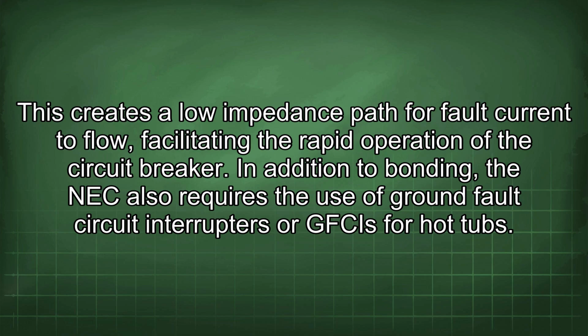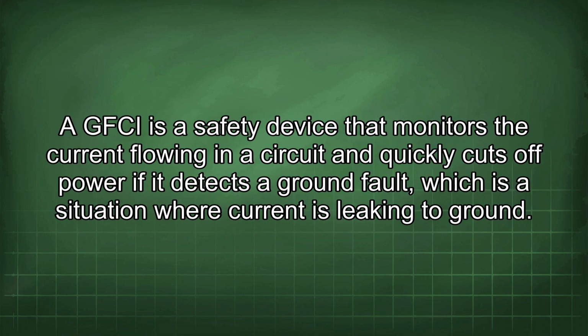This creates a low impedance path for fault current to flow, facilitating the rapid operation of the circuit breaker. In addition to bonding, the NEC also requires the use of ground fault circuit interrupters, or GFCIs, for hot tubs. A GFCI is a safety device that monitors the current flowing in a circuit and quickly cuts off power if it detects a ground fault, which is a situation where current is leaking to ground.